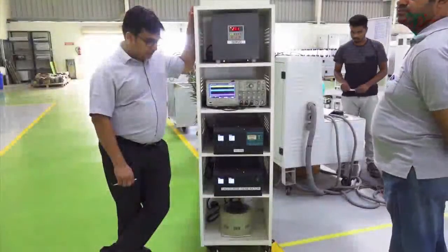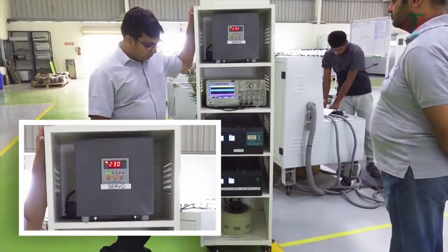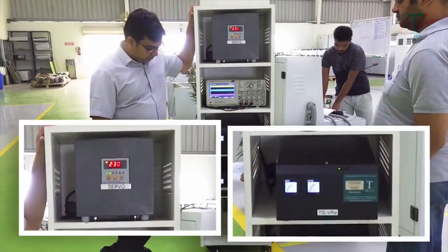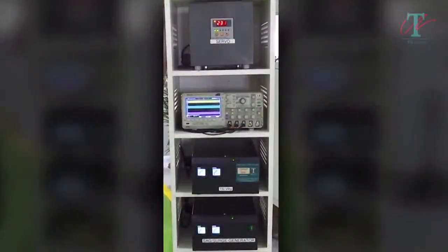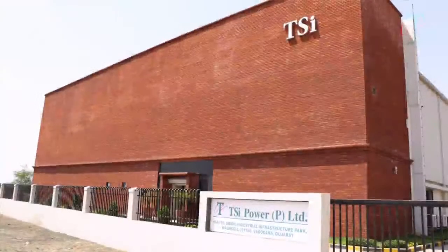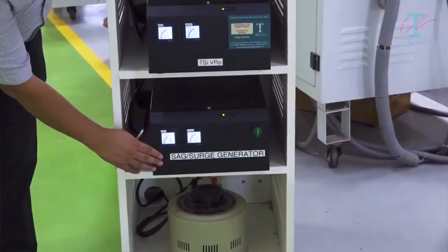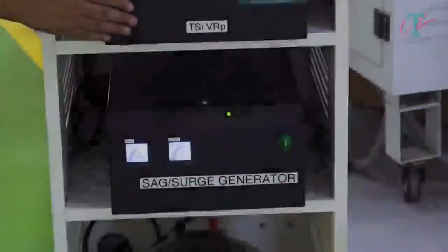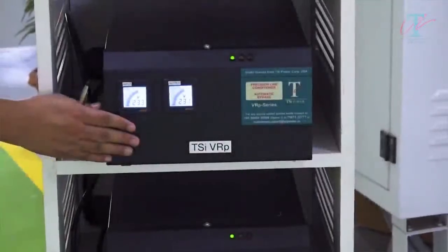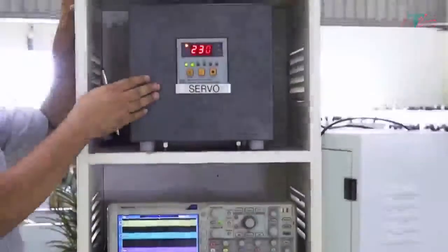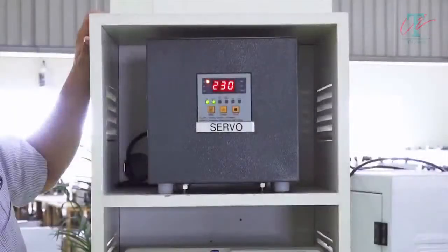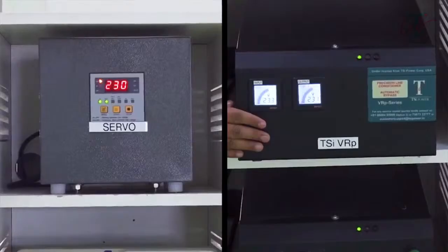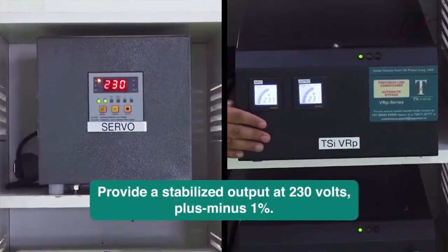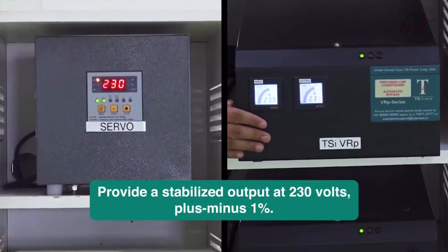Let us now witness a comparison of a typical servo voltage stabilizer with our TSI VRP static voltage regulator, at a simple demonstration setup created in our factory at Vadodara in India. Here is a sag surge generator which supplies a nominal 230 volts to a static voltage regulator and also the same 230 volts to a servo voltage stabilizer. Both are designed to provide a stabilized output at 230 volts plus minus 1%.